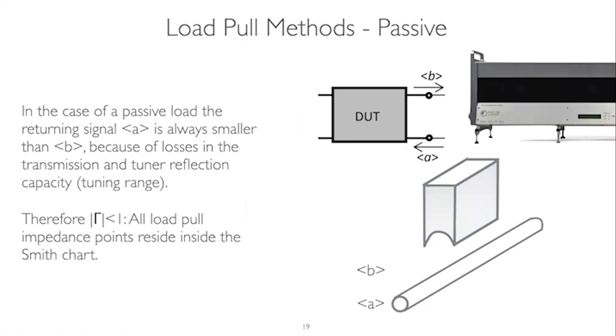Passive tuners are very well known, covering anywhere from 10 megahertz to 110 gigahertz and even higher. What I've drawn here is a central conductor and an RF probe. The RF probe is in the tuner, and that's what disturbs this B wave and sends an A wave back. Let's say we take a tuner that's initialized, meaning the probe is totally retracted, and we send a B wave through the tuner. The B wave will just go right through the tuner and not be affected whatsoever, like sending a signal through a cable, a low loss airline. It basically just flows through the tuner and is not reflected back.